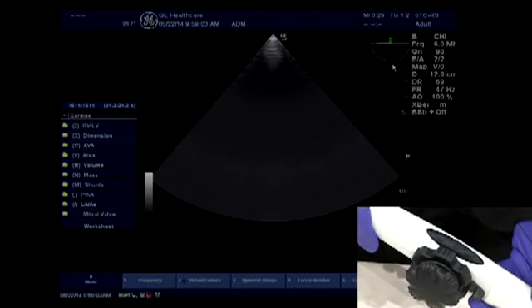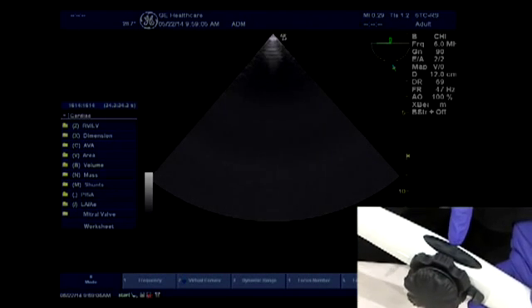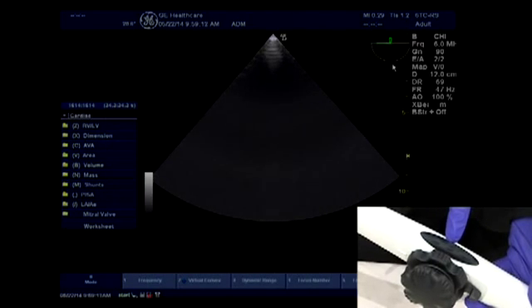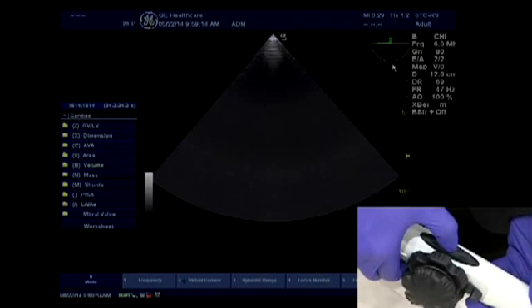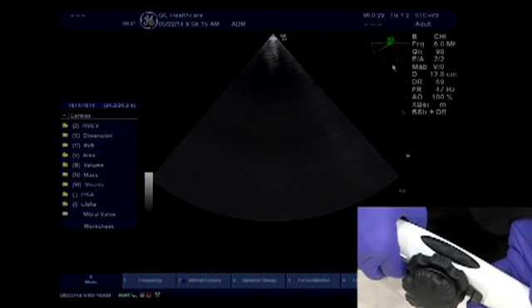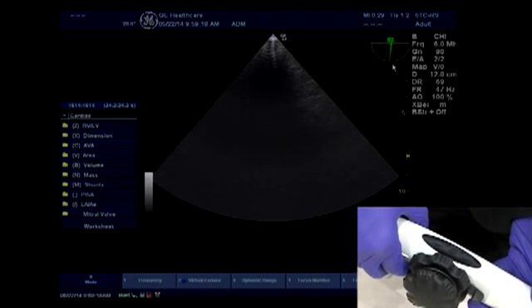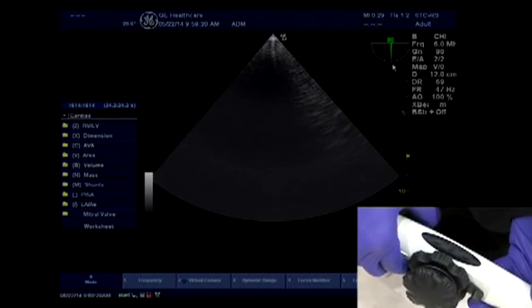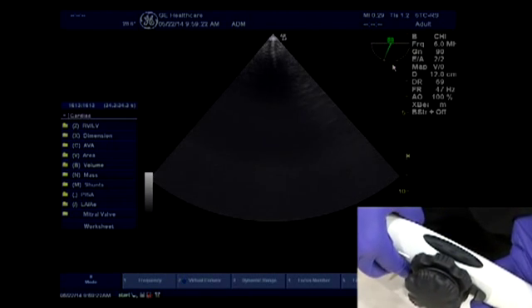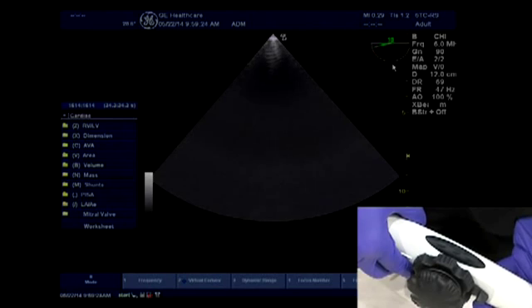Operating the biplane functionality. The biplane button is located directly between the scan plane controls on the endoscope handle. This rotates the scan plane at a full speed directly to the orthogonal angle. If the scan plane button is pressed again, the scan plane rotates back to the original position.